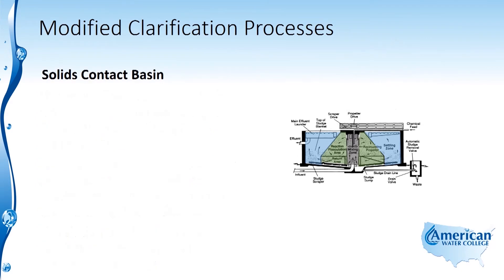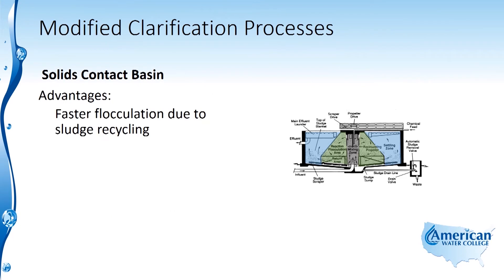The advantages of the solids contact basin are that it allows for faster flocculation due to the sludge recycling, and it has a shorter detention time so you can handle higher flow rates.